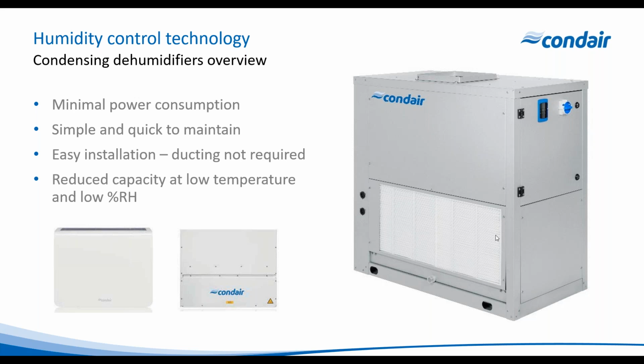But the big consideration is that if you're looking for a lower humidity, the condensing unit will not do it for you. For applications where you're looking to control around 20 degrees C and 50% RH, these are ideal. If you're looking for 15% RH, you'll never achieve it with a condensing dehumidifier, because you're limited by the evaporating temperature of the refrigerant, making sure that it doesn't get too low, where it can cause the condensate to freeze on the evaporator coil. So you're limited to typically, say, 19 to 21 degrees C and 50% RH.